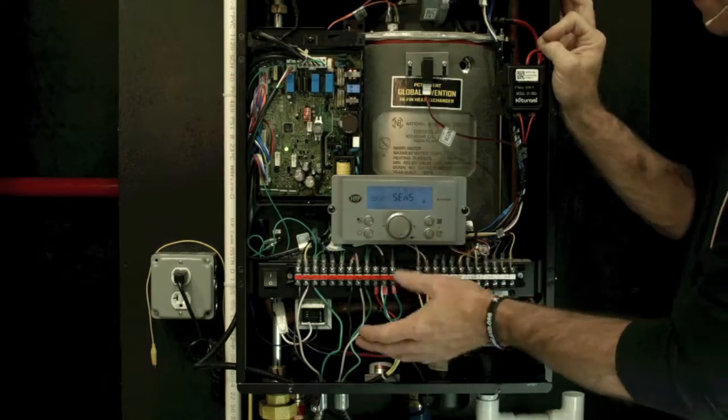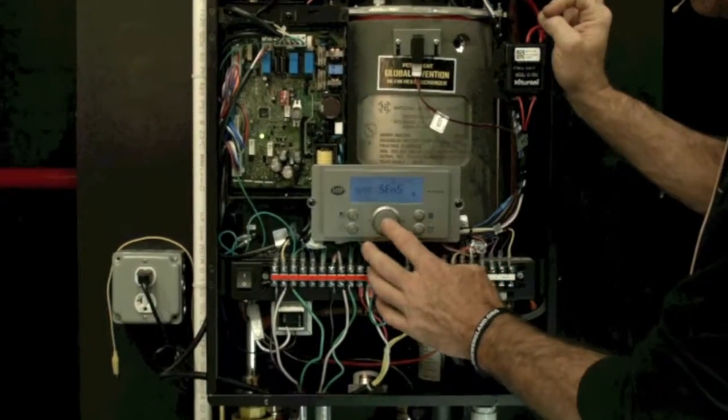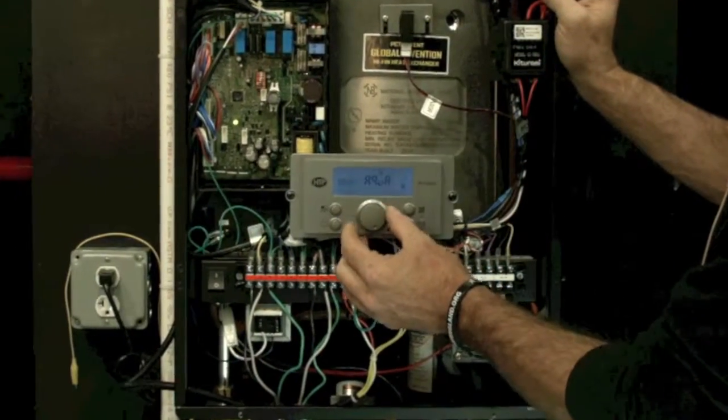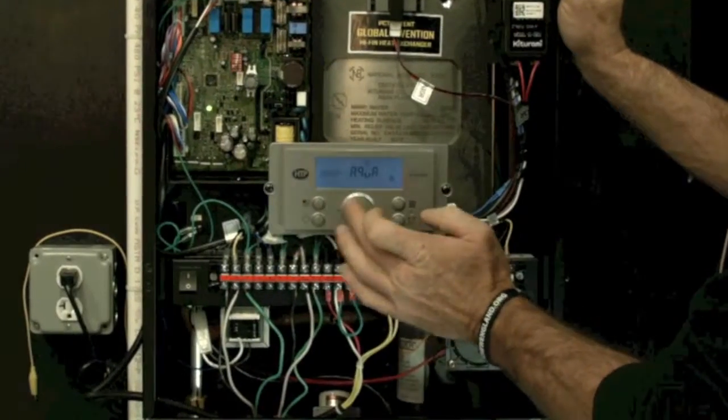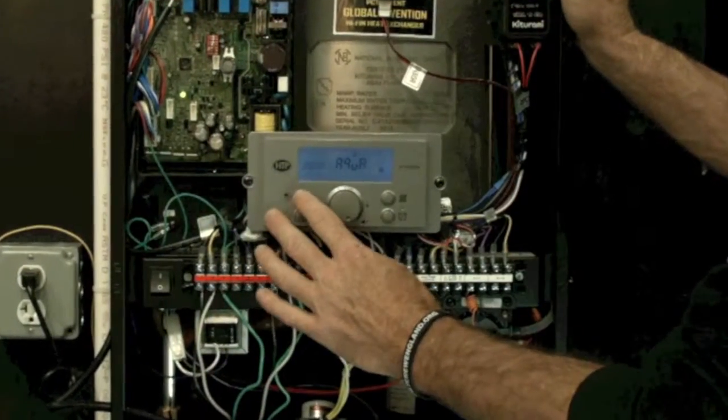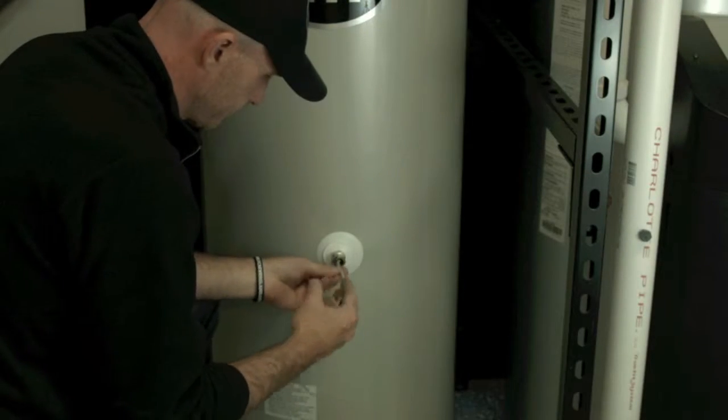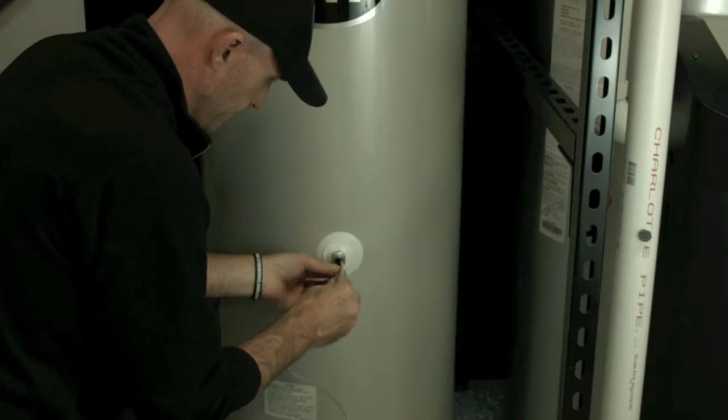This error will go away if an Aquastat is installed and parameter 39 is changed to Aquastat option and the boiler is powered off and then back on, or a defective DHW sensor is repaired or replaced.